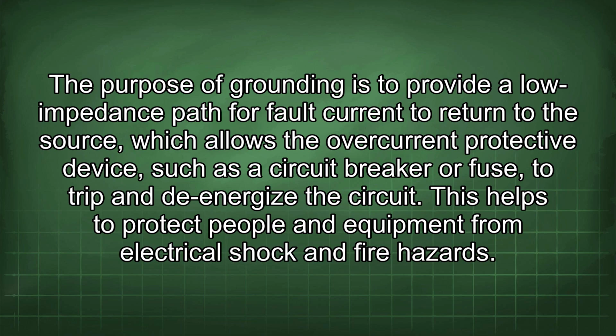The purpose of grounding is to provide a low impedance path for fault current to return to the source, which allows the overcurrent protective device, such as a circuit breaker or fuse, to trip and de-energize the circuit. This helps to protect people and equipment from electrical shock and fire hazards.